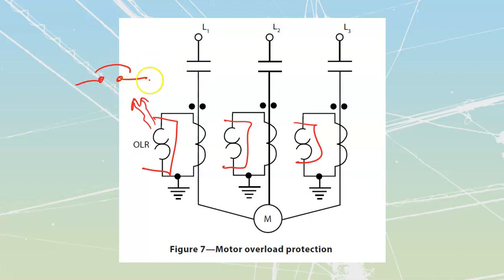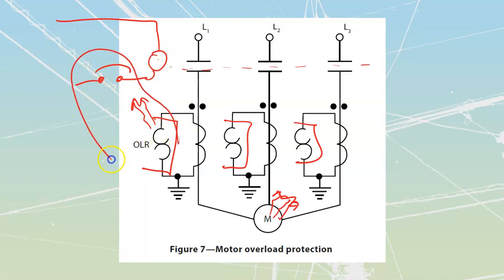It's going to cause something to trip, which will then trip out the actual coil that is energizing your motor. So if the motor is working too hard, we're going to draw some heat coming off the motor over here. Working too hard right now, it's going to be drawing too much current, which is going to cause too much heat at the overload heater, which is going to trip the little thermal element that is inside of that overload itself, which in turn is going to open up or kick out my coil.